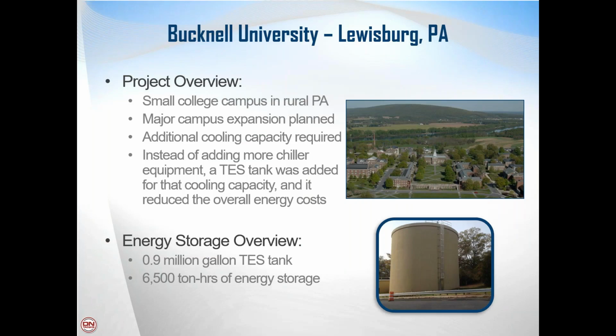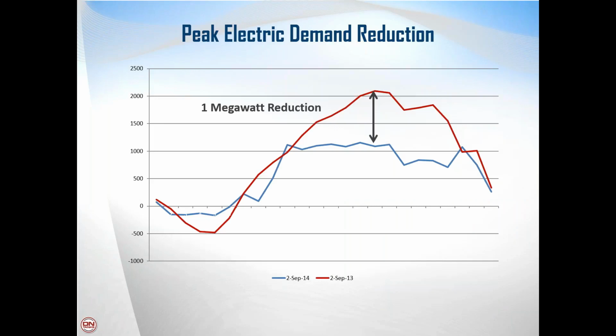Here's a couple of case studies I'm going to show you. This is a small college campus, Bucknell University in rural Pennsylvania. They were looking at expanding their campus, and so they were considering, do I add more refrigeration equipment or do I add a thermal energy storage tank to my campus? And they chose to not add additional chiller equipment, but instead they added a 900,000 gallon thermal storage tank to their campus. And by doing so, they reduced their electric demand by 1 megawatt on their campus.